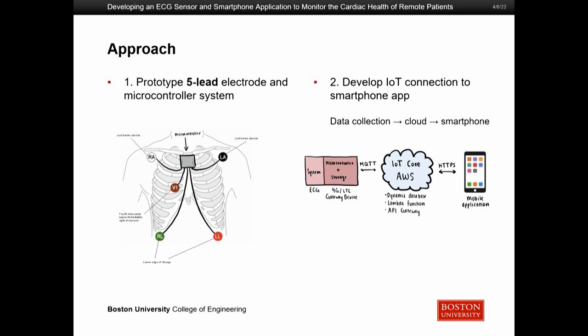We realized it's really hard to know where exactly to place the electrodes. So we used silicone to create a patch that you can stick on yourself — it already has the electrode placements built in. As a patient, all you have to do remotely is put this patch on. We also created a system including a phone application that takes all data from the ECG device, sends it to AWS IoT Core, which handles signal quality processing, storage into a database, and sends alerts to patients through the mobile app.